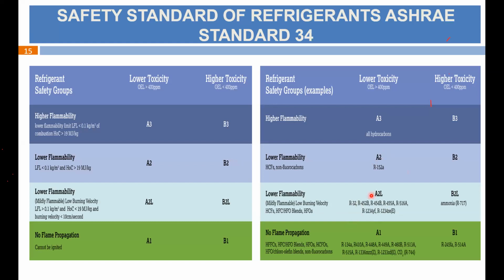These categories are mildly flammable, and I'll come to these refrigerants in the next slide. These are all blends of HFC and HFO refrigerants. And this R1234YF is an HFO refrigerant, tetrafluoropropene, mainly also used for mobile air conditioning, automobile air conditioning. Another is R1234ze. Ammonia comes under R717.